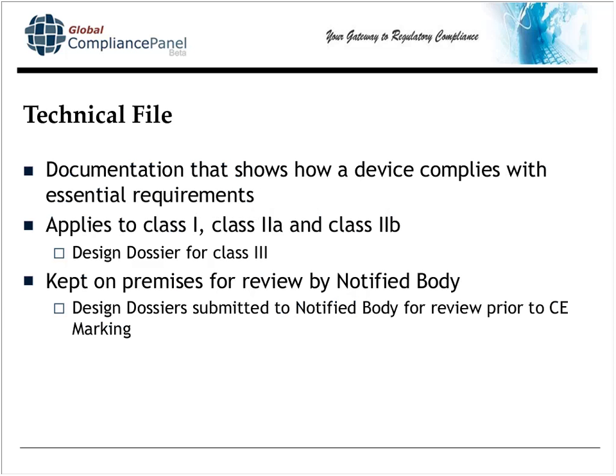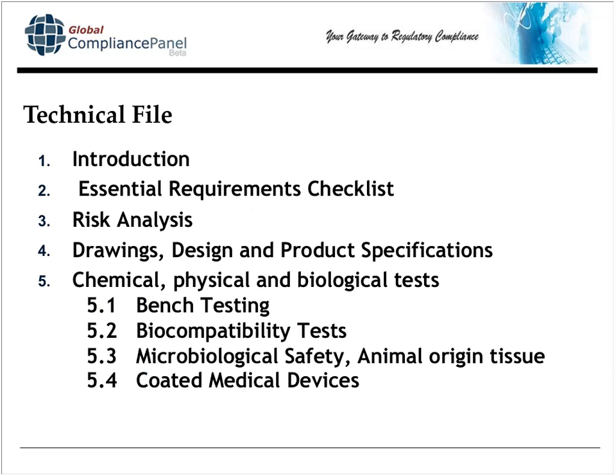The technical file is a document that shows how your device complies with the essential requirements. It applies to three classes: Class 1, 2A, and 2B. For Class 3 design dossiers, it's the same contents as the technical file, but you submit them to your notified body prior to getting your CE marking, whereas your technical file you just keep and they review it during their notified body audits. The structure of the technical file begins with an introduction, then the ER checklist, then a risk analysis, followed by the more technical aspects of the device — drawings, design specifications, product specifications — then all of the chemical, physical, and biological tests, and then the clinical data.